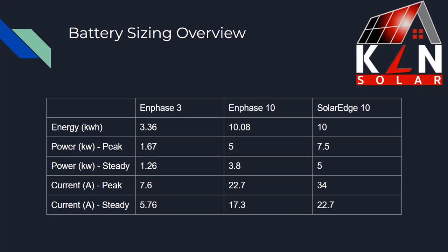You can see you've got a peak output of 5 kilowatts, a steady output of 3.8 kilowatts. That gives you a peak current, how many amps can you back up, of only 22.7, and you can only have 17 amps steady backup. Compare that to the SolarEdge 10, you've got a 7.5 kilowatt peak, 5 kilowatt steady. That's quick math, about 50% larger for the same size battery. It gives you a 34 amp peak breaker size that you can back up, and 22.7 steady. So it's a more robust backup on the same size battery.